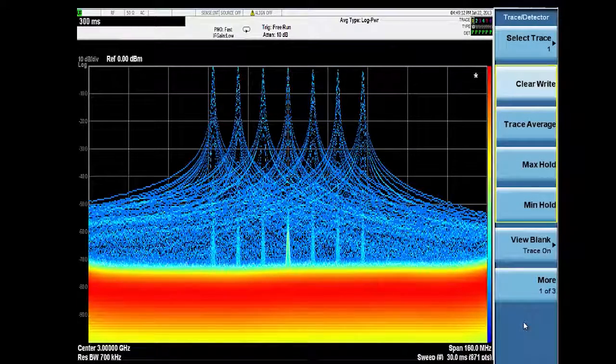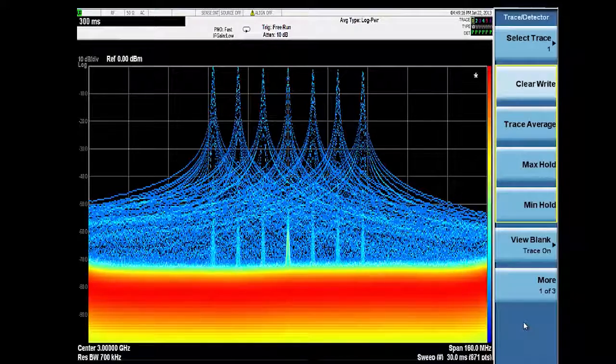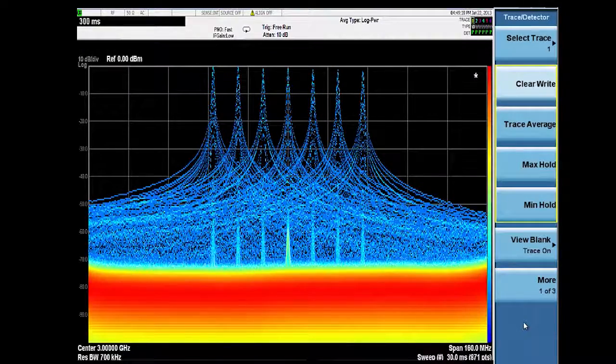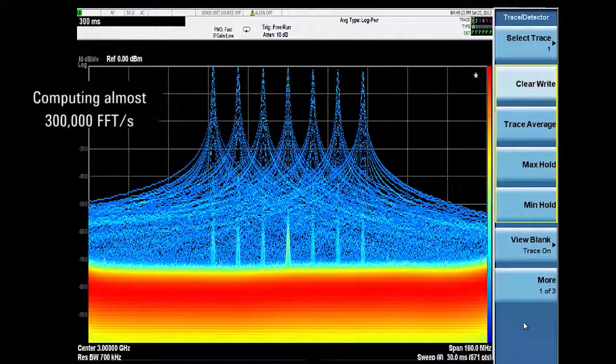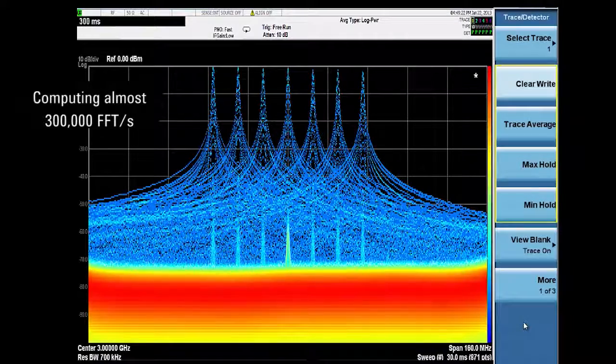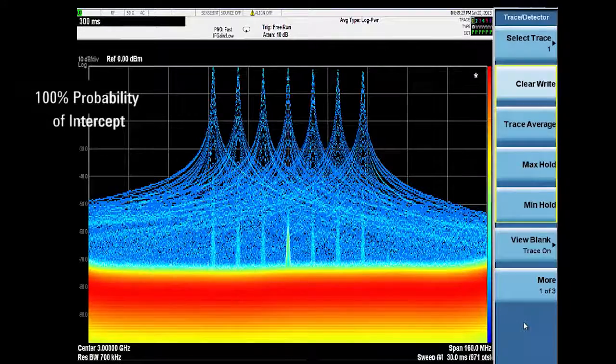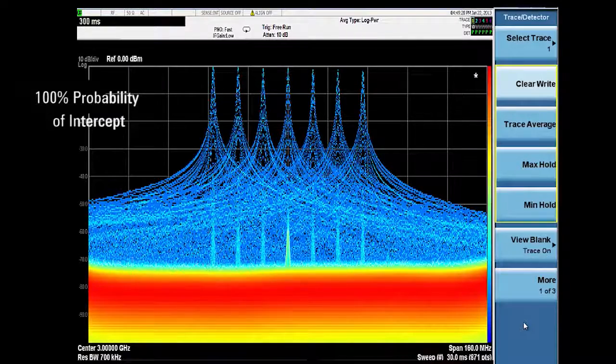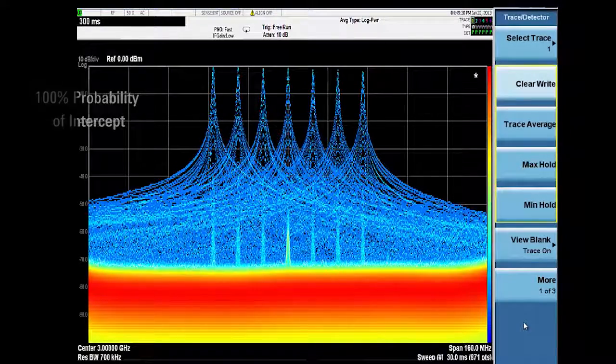Real-time mode can display both the real-time spectrum and power versus time. The real-time spectrum works by computing almost 300,000 FFTs per second on overlapping memory registers to give an industry-leading 100% probability of intercept on any signal longer than 3.57 microseconds.